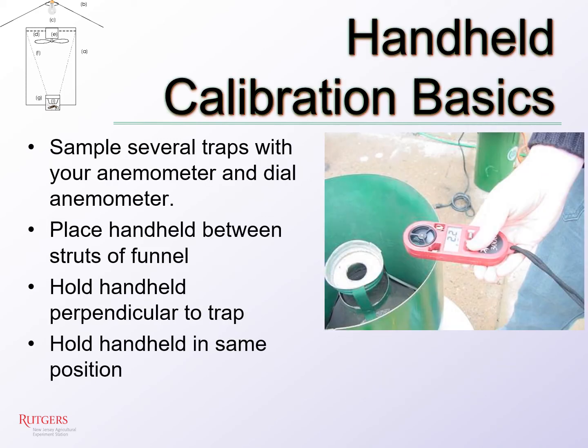If you have a handheld anemometer, you can calibrate it to the dial anemometer to determine the values of the lower and upper limits of a correctly running trap. To do this, you should sample several traps with both your handheld and the dial anemometer. Take a minute reading with the dial anemometer, write that value down, adjust it with the correction factor, and remove the anemometer. Place your handheld anemometer such that it is between the struts of the funnel located inside this trap.